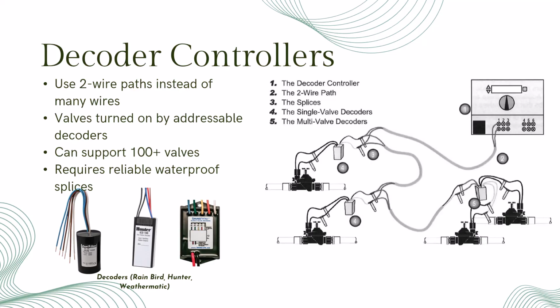Decoder systems are a game changer for large installations. Instead of running wires from the controller to each valve, you only need a 2-wire cable. Each decoder is installed near a valve and has an address. When the controller sends a command to that address, the decoder turns the valve on. This setup supports dozens to hundreds of valves, and it cuts down dramatically on wiring costs and complexity.